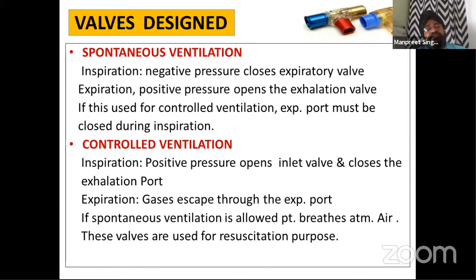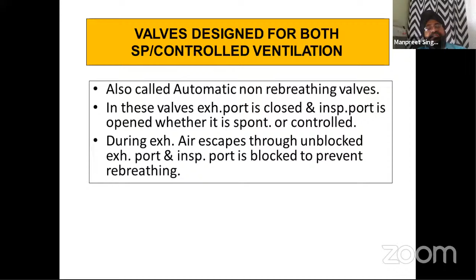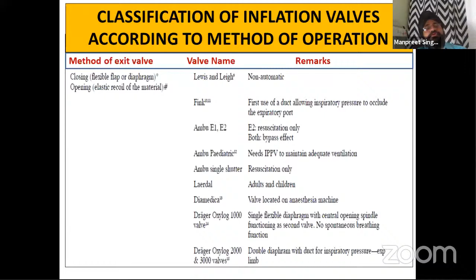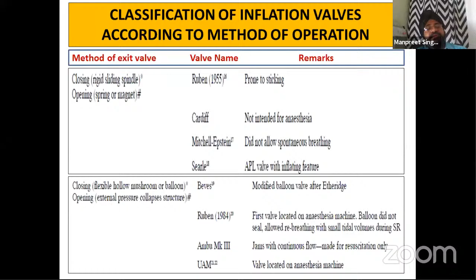And there are certain valves which are designed for both spontaneous and controlled ventilation. These are called automatic non-rebreathing valves. And in these valves, the exhalation port is closed and the inspiratory port is open, whether it is spontaneous or controlled. Then there are certain other classifications also. This I have taken from Anaesthesia 2017, a fresh article just 4 years back. And they have given this classification of inflation valves according to the method of operation. It is a method of exit valve. If you see that, it can be closing or opening, and all those valves which I have already discussed are included in this. It is just to see which one is the opening one and which one is the closing one. This table you can see there in Anaesthesia 2017.